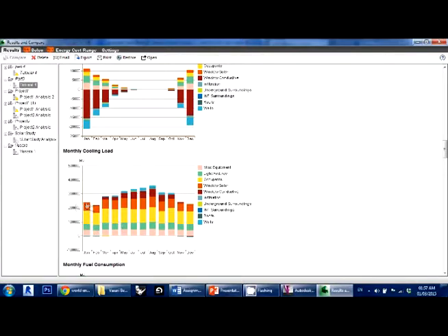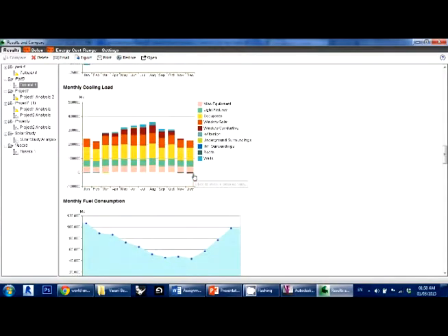So we have to compensate for this to get to the comfort zone of the occupants inside the building. For example, in June, July, and August, the three high months here, the three summer months, we need nearly 350,000 megajoules from our HVAC system to compensate this heat.